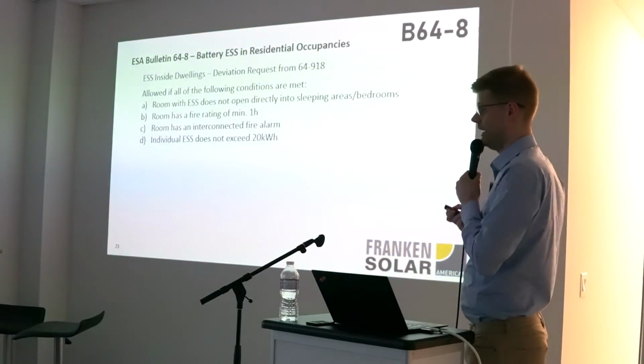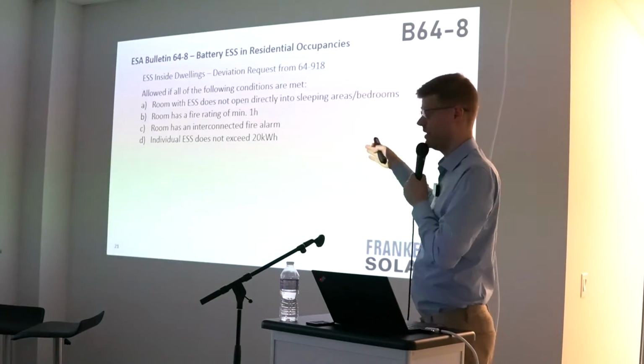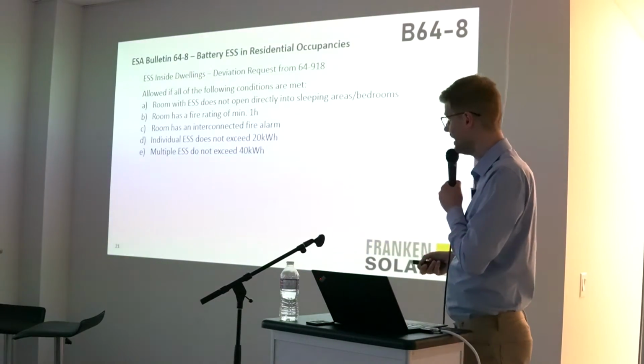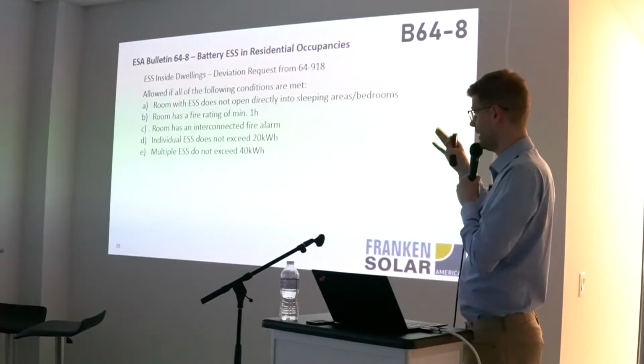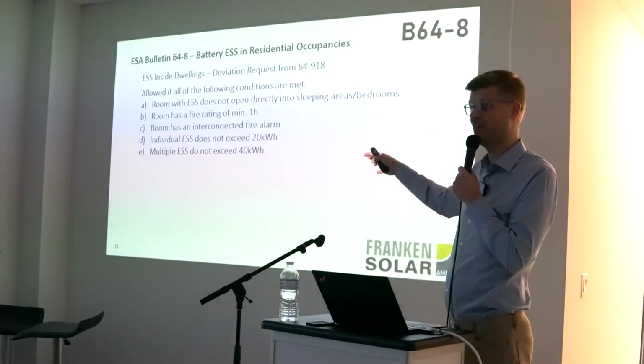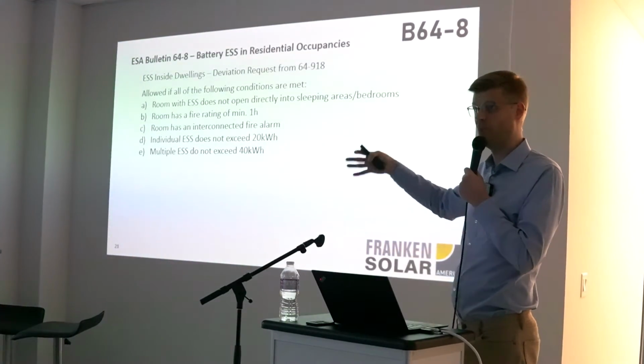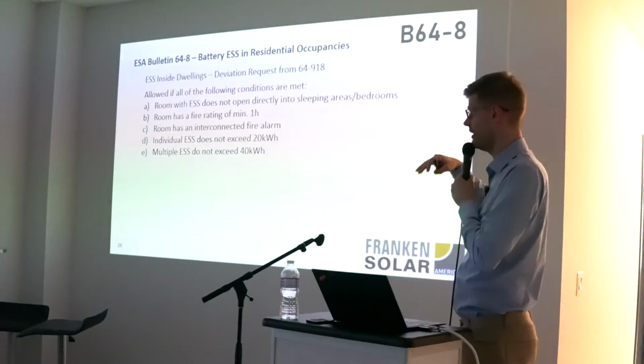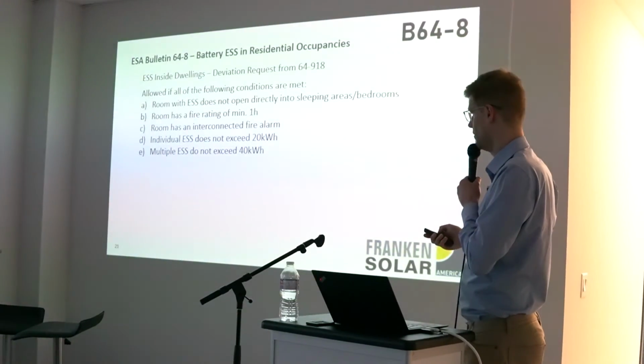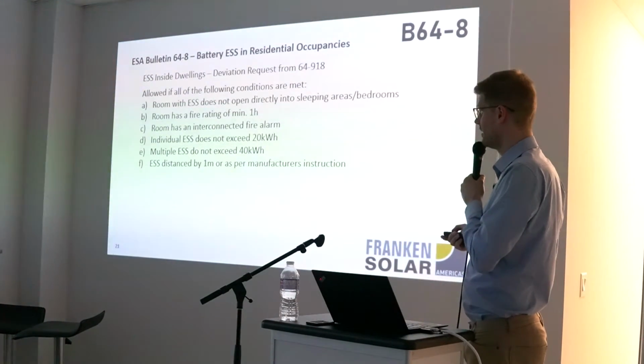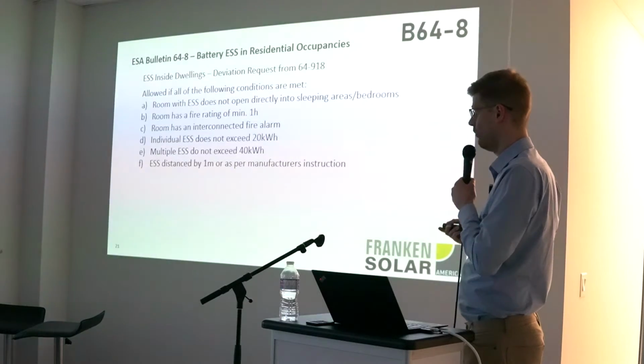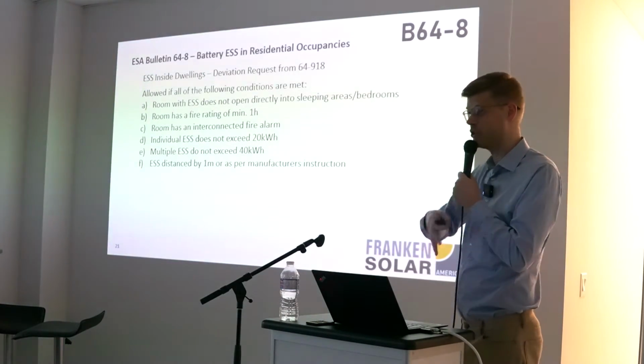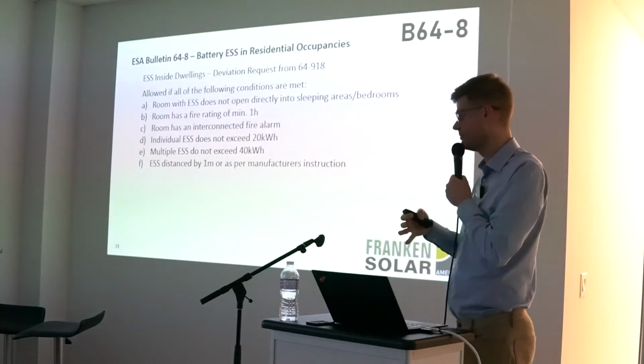The individual energy storage system cannot exceed 20 kilowatt hours, and multiple systems cannot exceed 40 kilowatt hours, and we have seen that before. These are the limitations anyways for a residential install in a residential dwelling. And you have to have a minimum distance of 1 meter between each increment of up to 20 kilowatt hours.